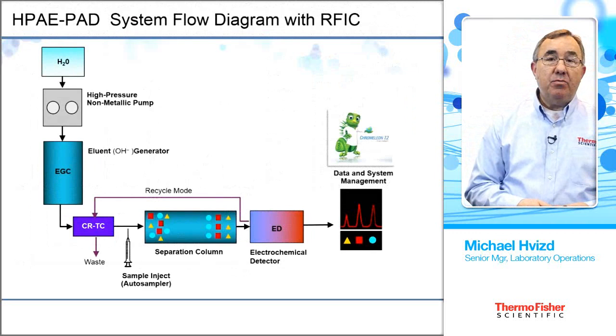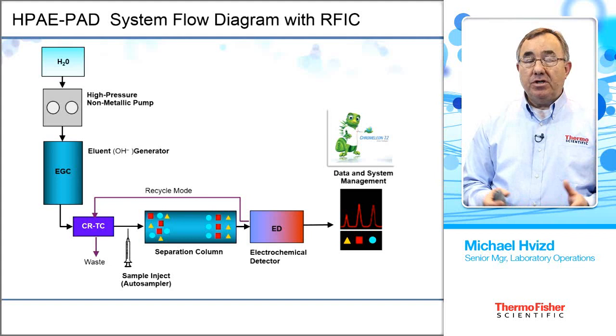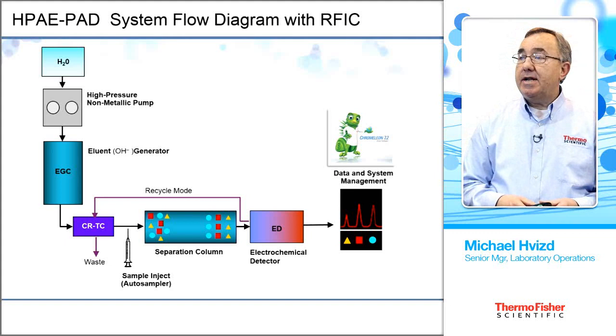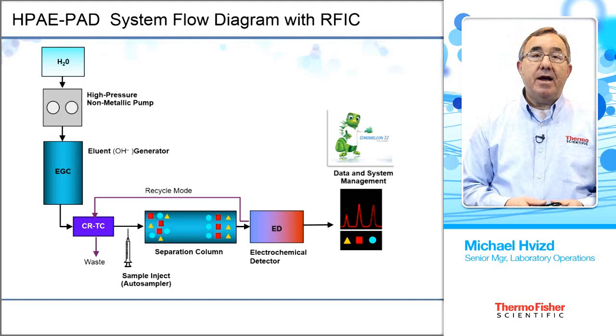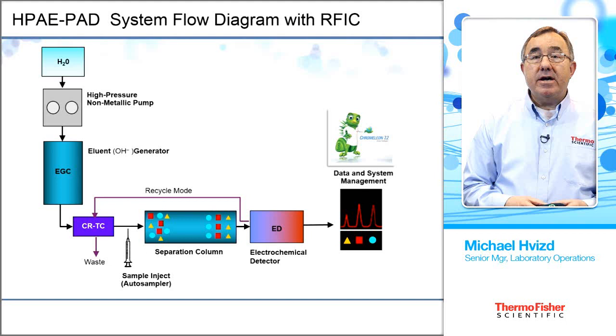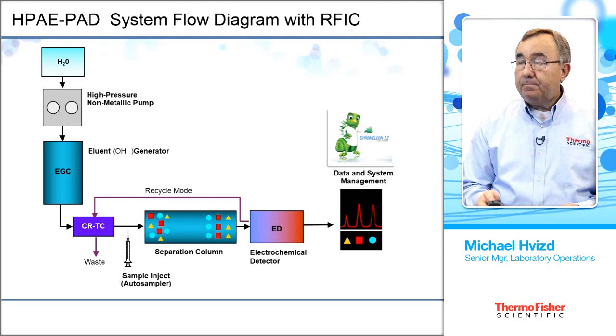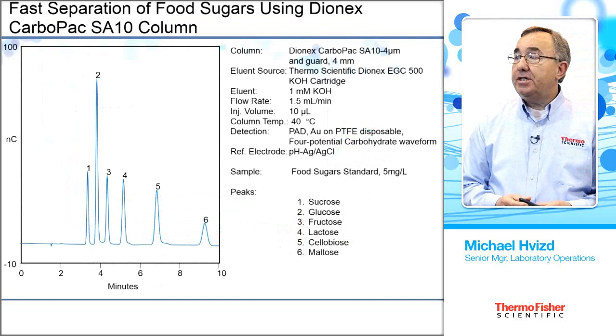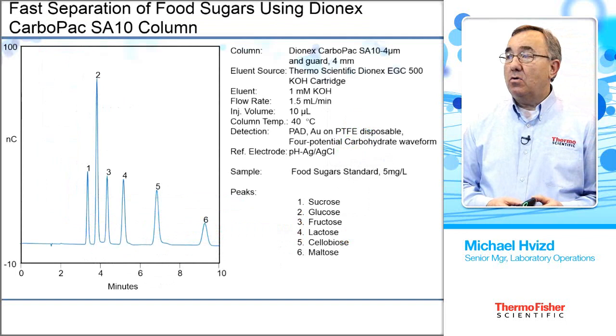Now let's get into some new technology that enables even faster separations, with new columns developed to take advantage of it. This diagram illustrates where the eluent generator fits into a carbohydrate analysis system — similar to its role in standard conductivity detection. After the eluent generator and after the CRTC (continuously regenerated trap column to remove anionic contaminants), we do our separation and then route directly to the electrochemical detector. Our first separation uses the new SA10 column, developed for fast separation in biofuels, foods, and beverages, using a very low concentration of hydroxide — one millimolar only — with a separation done in about 10 minutes.